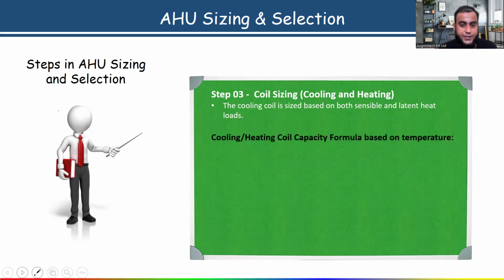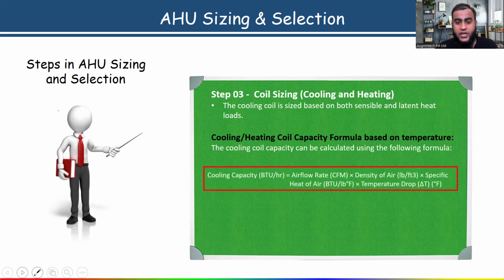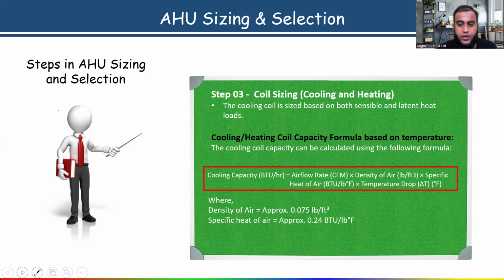And here the cooling or heating coil capacity formula is written, to find the capacity based on temperature. So try to understand this formula. Cooling capacity in BTU per hour is equal to airflow rate in CFM times density of air in pounds per cubic feet times specific heat of air times temperature drop in degrees Fahrenheit. Density of air, all of you know, how much density do we consider for air? 0.075 pounds per cubic feet. And specific heat of air is approximately 0.24 BTU per pound degree Fahrenheit.